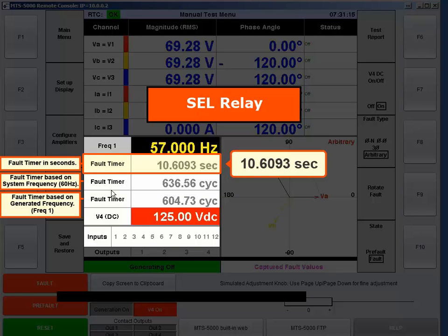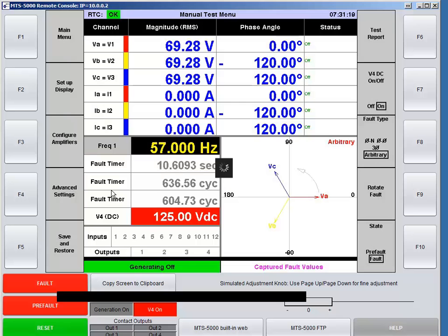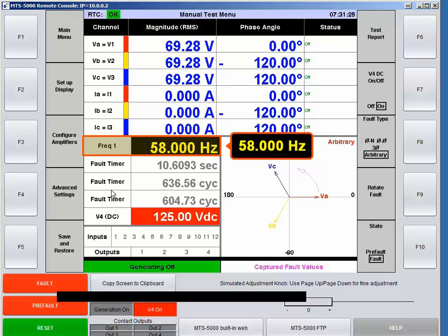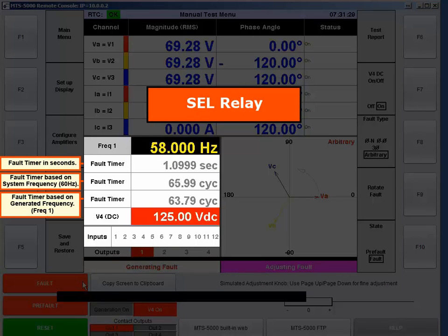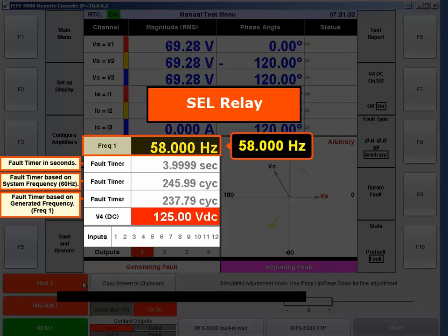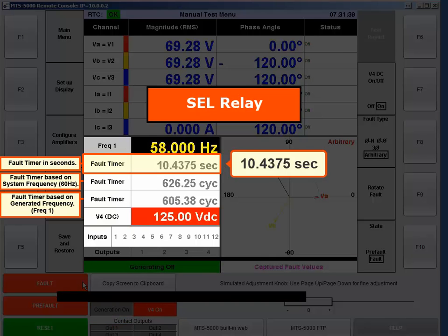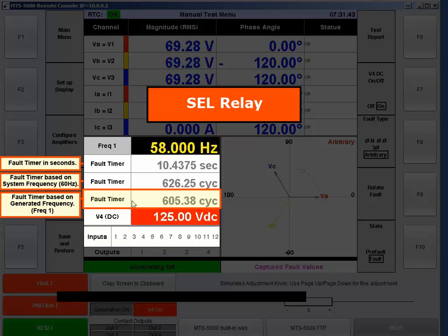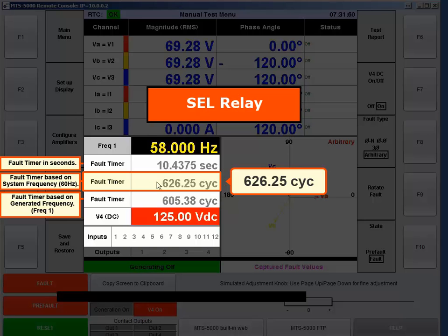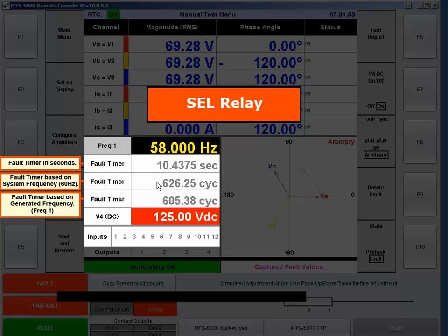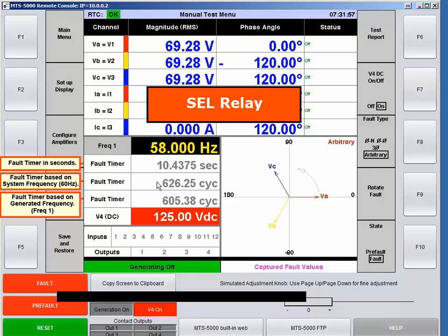The time shows 10.6 seconds, which is something everybody should understand: because this relay uses the injected frequency to count cycles, the time in seconds will differ when I change the frequency. At 58 Hz the trip came in at 10.43 seconds, and the bottom fault timer still reads around 600 cycles while the 60 Hz-based timer shows 626 cycles. You can see how easy it is to get the wrong number if you don't know how the relay or test set calculates cycles.